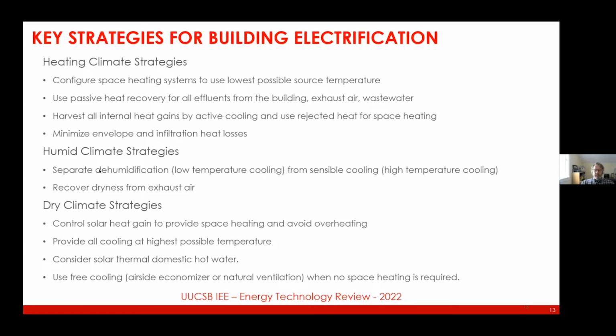Humid climates, different strategies. Important strategy whenever you're doing dehumidification is to separate the dehumidification from the sensible cooling, because the dehumidification requires low temperature. You have to take some volume of air down to a temperature generally lower than about 53 or 54 degrees Fahrenheit to get a dew point temperature that will be consistent with maintaining comfort conditions in the space, which is 75 degrees Fahrenheit, 50% relative humidity, which is a 55 degree dew point. So doing the arithmetic, and what's really interesting, much of the analysis for these kinds of things is really accessible, at least in a sort of back of the envelope way, by very simple arithmetic. So we want to separate this dehumidification, because we need the low temperature cooling to do that, from the sensible cooling, which we can do with a much higher temperature.